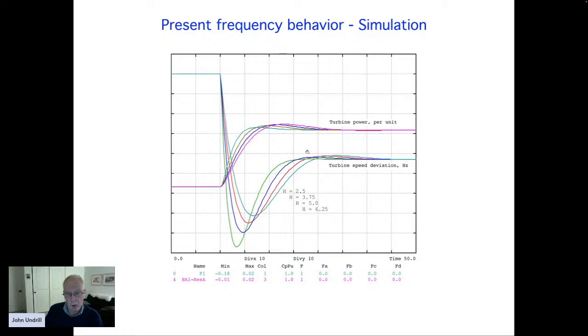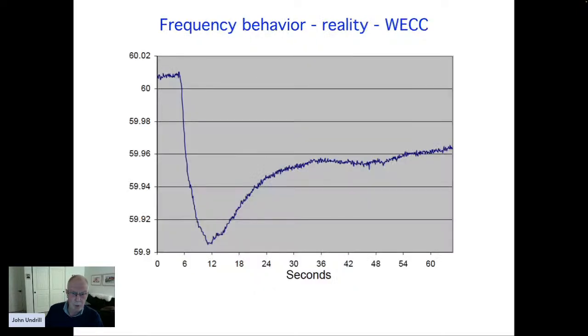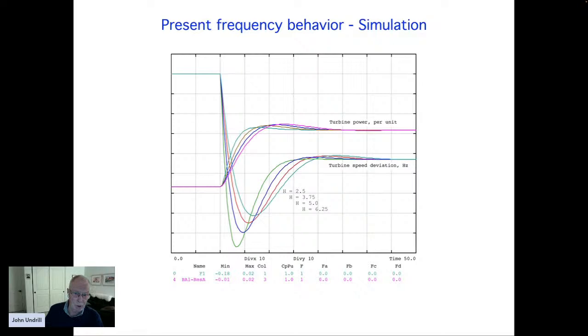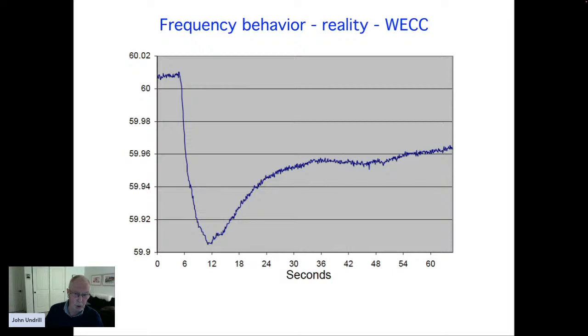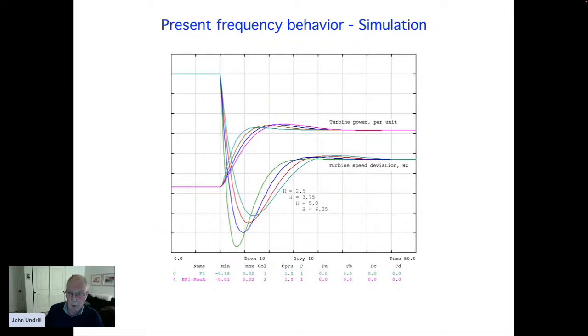If you know the inertia of the system, you should be able to get your simulation to match reality, so that this is reality and this is a simulation, and you can believe what you see in the simulation. You do this simulation with programs like PSSE or PSLF, Power World. There's a DigSILENT, a European program that does this. There are half a dozen trusted, well-proven simulation programs, which if you set out to simulate what the grid does in reality, will get a very good approximation to what it does by mathematics.